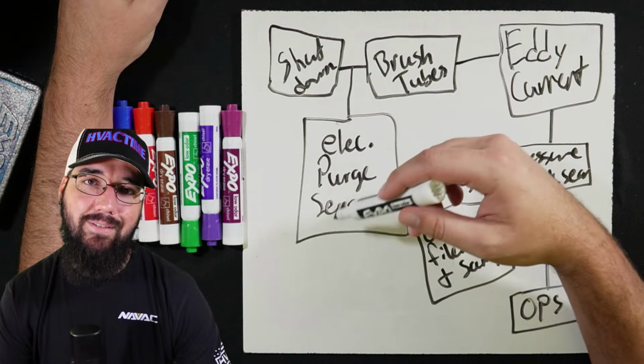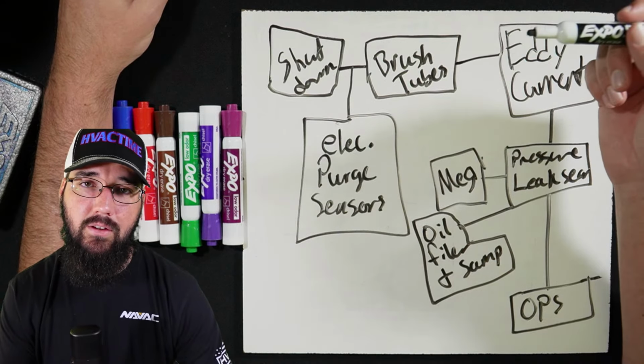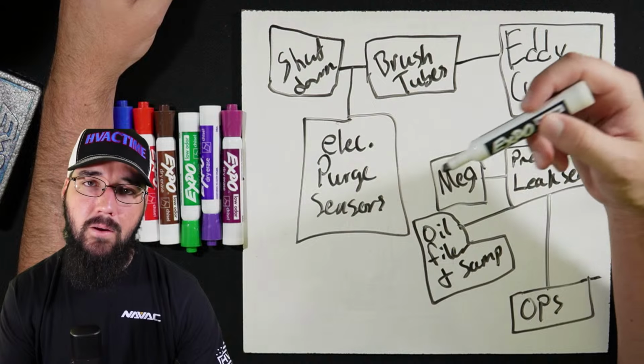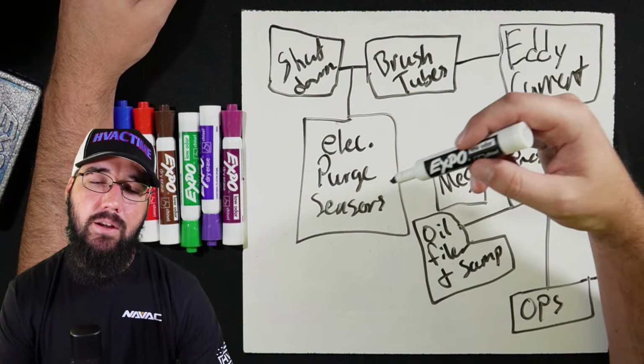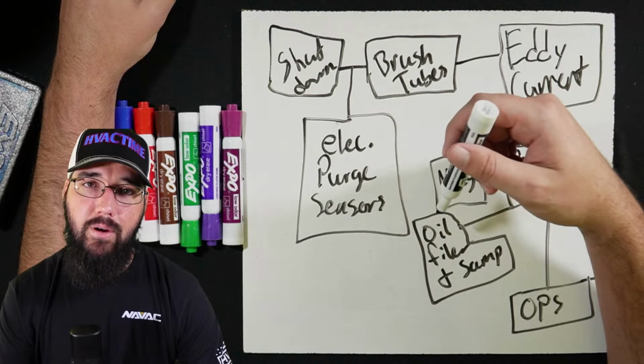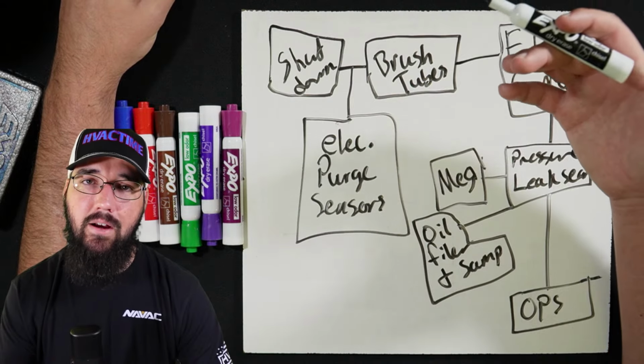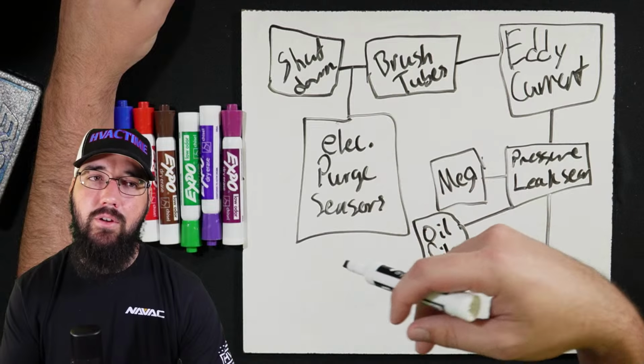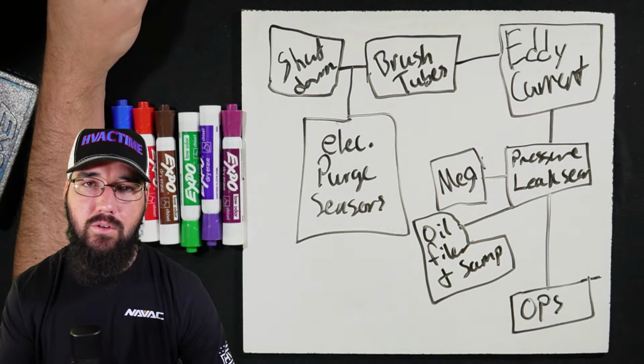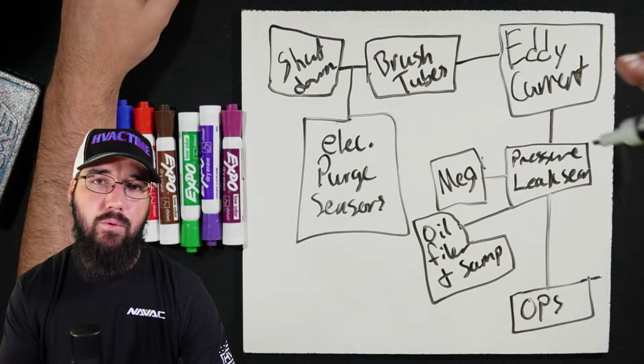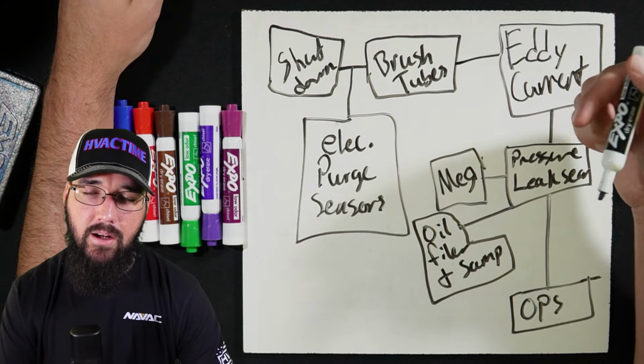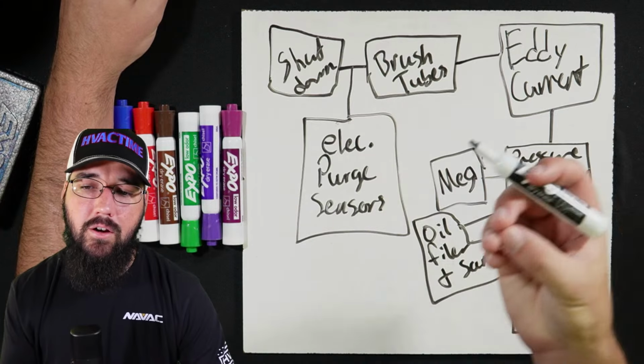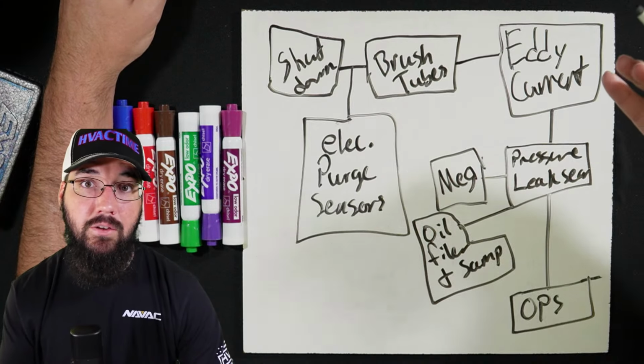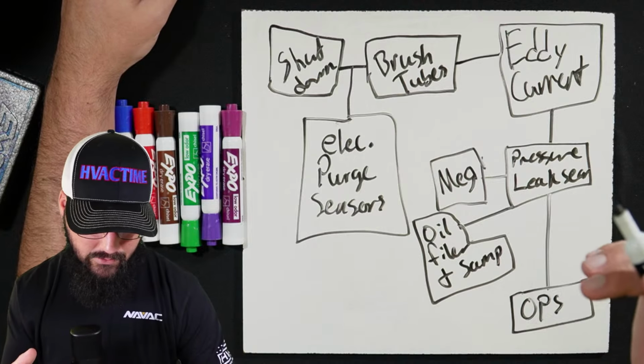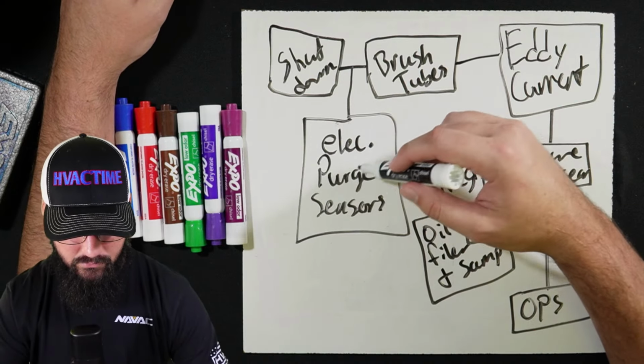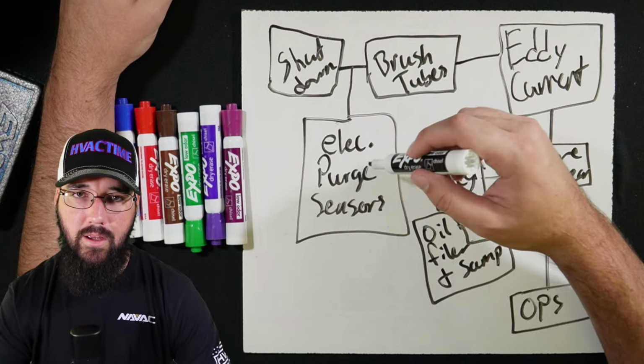That's not a problem. We have to isolate the purge, right? So close the isolation valves, go into the purge unit, then do your purge filter, then pull an evacuation on those lines. Most systems should have a quarter-inch tap that you can hook even a small, fast little vacuum pump to. You're not trying to pull it down to 500 microns. We're just trying to get all the non-condensables that got drawn in during the maintenance process back out of there. That's the main point. Just do that.